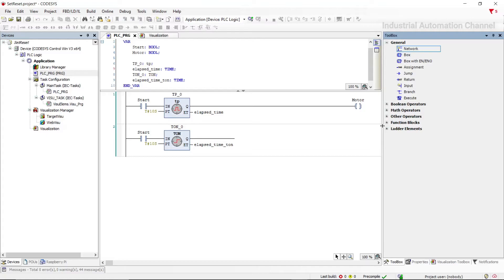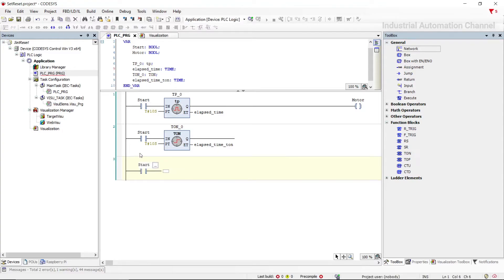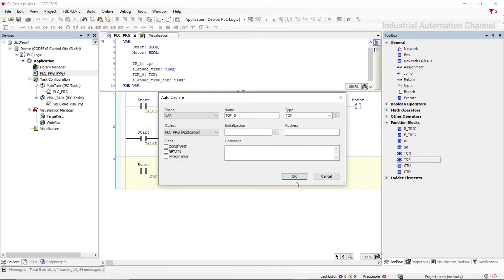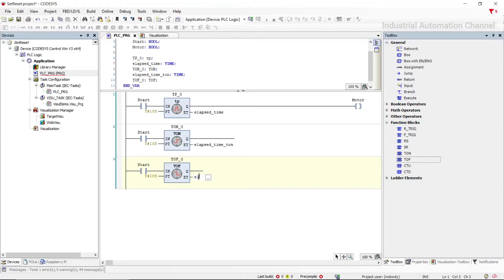Now let's talk about the last timer — Timer Off Delay, or TOF. This timer turns off the output after a delay. I insert it from function blocks into the programming environment. Like other timers, we need to declare a variable for the timer with data type TOF. The input is again our start button, the preset time is again 10 seconds as the delay time, and we have a variable for elapsed time with data type time.